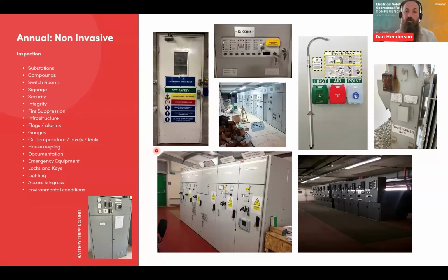6 months is probably tolerable. Quarterly, ideal. I always try to do monthly purely because I know things change week by week. So they definitely change month by month, and they're going to change year by year. Things like temperature changes, humidity level changes, dust and debris as your seasons change, load changes. There's so many things that can impact your network. It's good to keep close to the ground, but I appreciate there are constraints, possibly geographical locations, possibly the amount of resource, the size of your networks and things like that. So it's got to be reflective of what you've got, the risk that's there, and the criticality of the equipment. But I would say, as a minimum 12-month, 6-month ideal, but the more inspections you do, the bigger picture you've got for everything on your network.